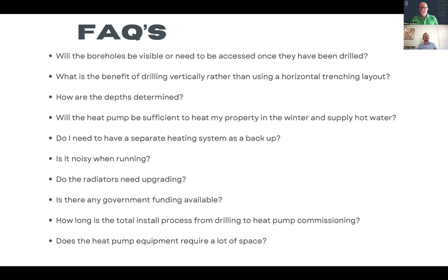What's the benefit of drilling boreholes rather than doing horizontal trenching? With boreholes, you can build something on top. We've done several projects, for example in London, where we drilled the boreholes at the ground level, then builders excavated, let's say, two levels down, and the boreholes are now under the building, because you don't have an amount of space. With horizontal collectors, we would recommend not doing anything on top. Putting any roads, buildings, sheds or warehouses on top would reduce their energy input from the rain, sun and so on, which then reduces their efficiency.